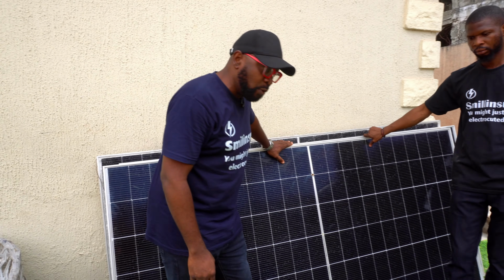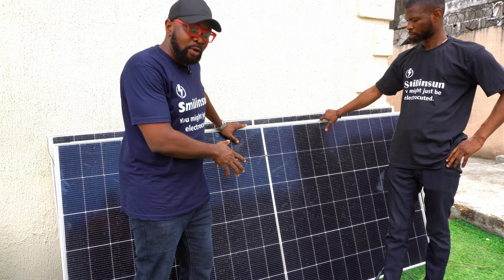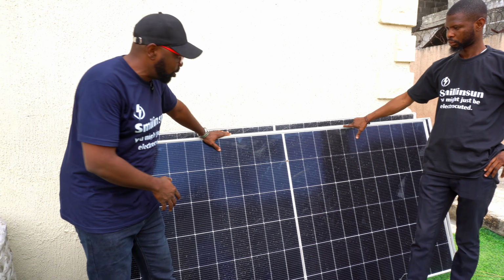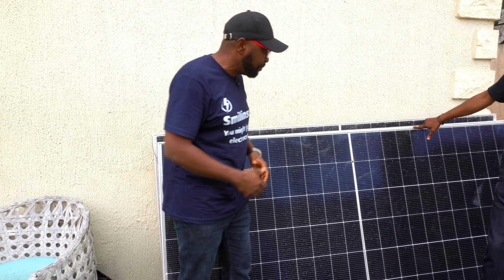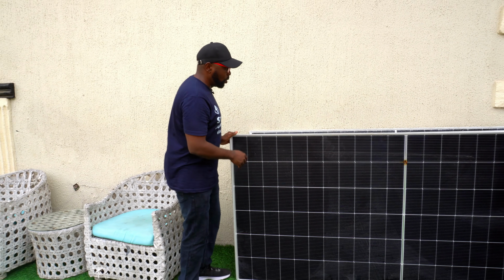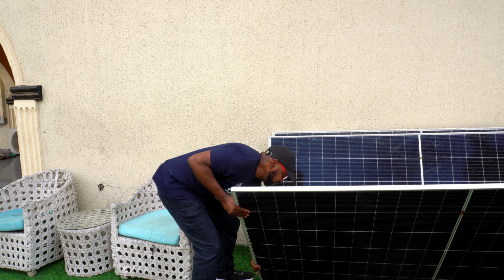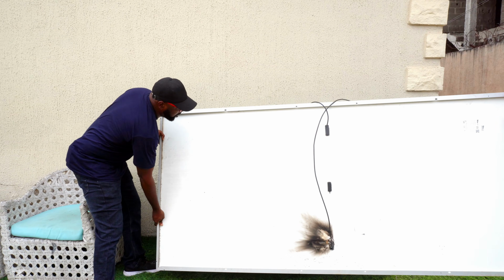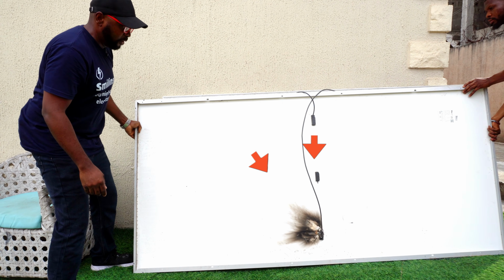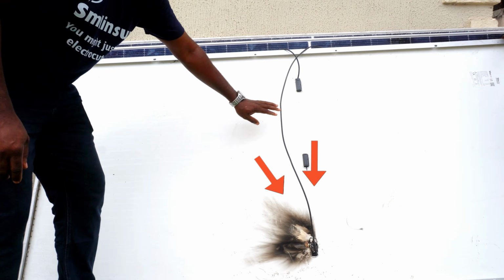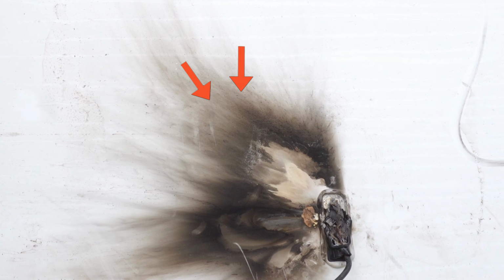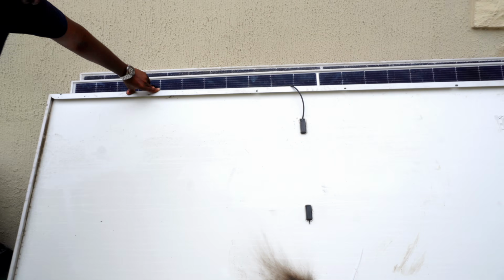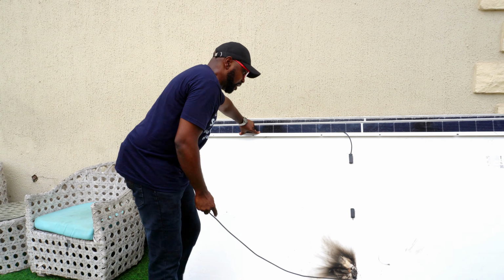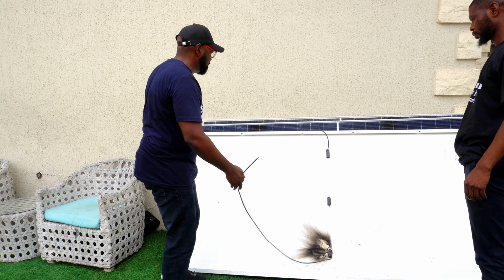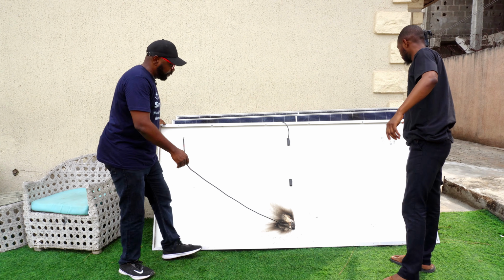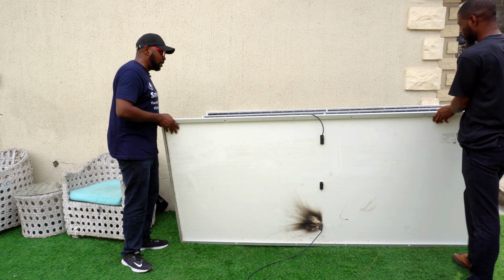It could also be a loose connection because we noticed they weren't using MC4 connectors for this connection. They were just cutting the wires and joining them. When we tested the solar panels, it wasn't producing anything anymore, just barely giving very low voltage. The current wasn't supplying at all. You can see it's completely burnt out, pretty bad. It wasn't supplying and it was also causing a huge breach in the entire connection, limiting almost everything generated from the solar system.